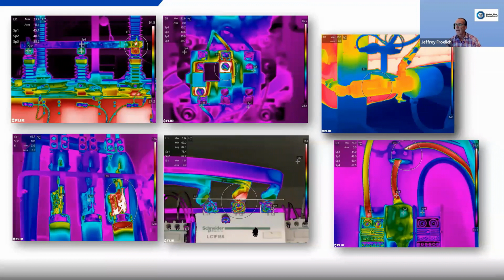heating. Up in the top left, you've got a combination of the two. You have a loose, deteriorated, poor contact surface integrity on that connection. And you actually have induction heating because they put a C-clamp on that thing, and it was of dissimilar metals. So you've got two competing metals that can't live in the same space, if you will. So there's a reaction happening there.